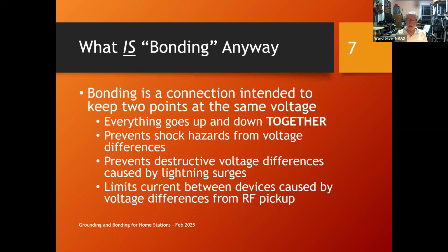That's when you have a shock hazard, so bonding is important there. Lightning surges can cause enormous destructive voltage differences because of the amount of current involved and the strong magnetic fields. You can generate incredible voltages in conductors, surprisingly high. So by bonding all your equipment together, even if there's a lightning surge through the station, you keep everything together.